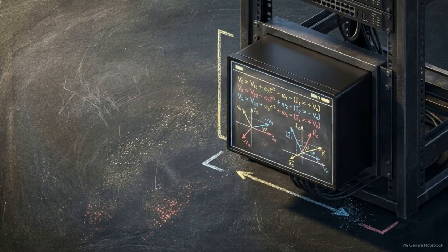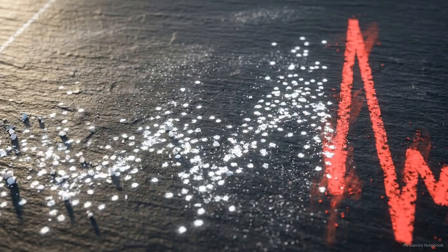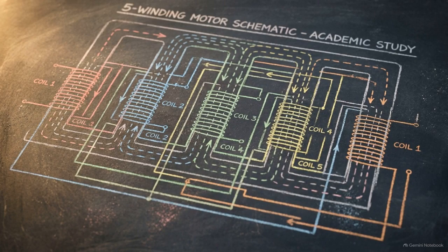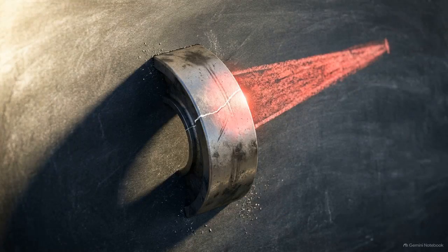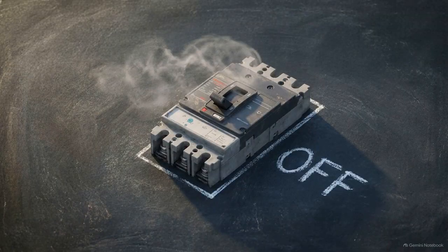Modern microprocessor-based protection relays calculate instantaneous symmetrical components. They sample the incoming current thousands of times per second, hunting for the exact moment those negative sequence values spike. These same diagnostic principles are being written into the control logic of next-generation 5-phase and N-phase electric drives. By isolating that specific negative sequence signature, a digital relay can detect a microscopic mechanical failure and trip the breaker, long before the heat and vibration lead to a catastrophic mechanical breakdown.